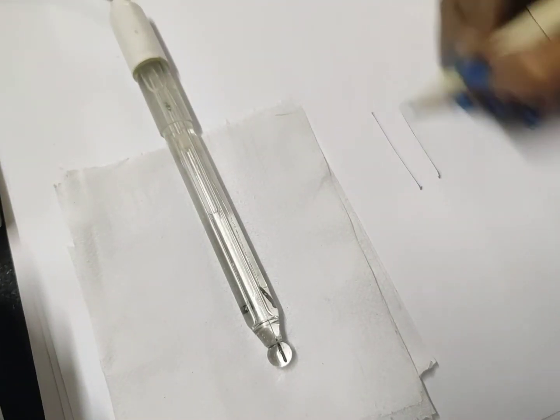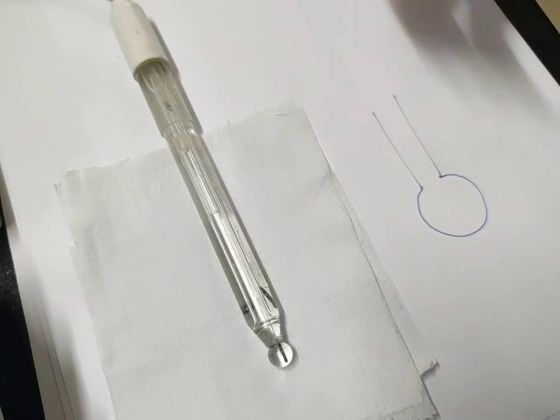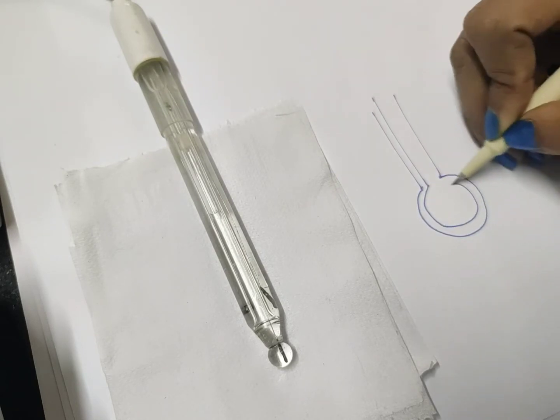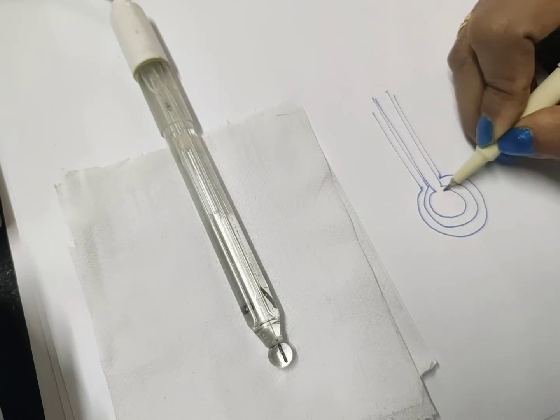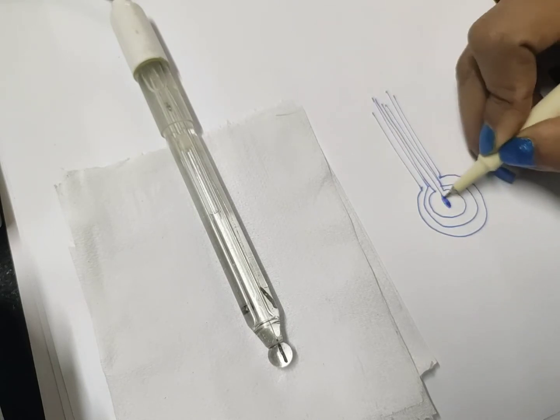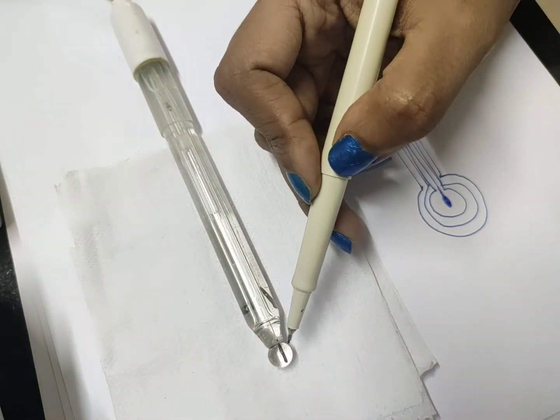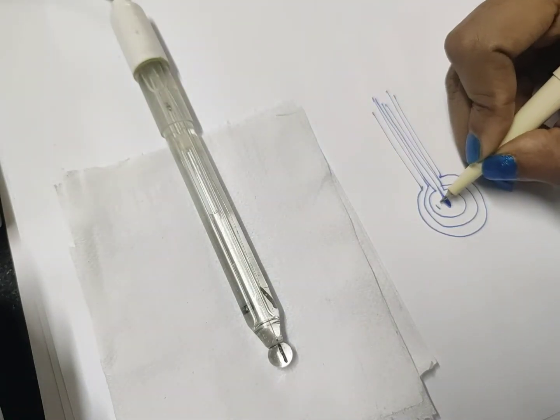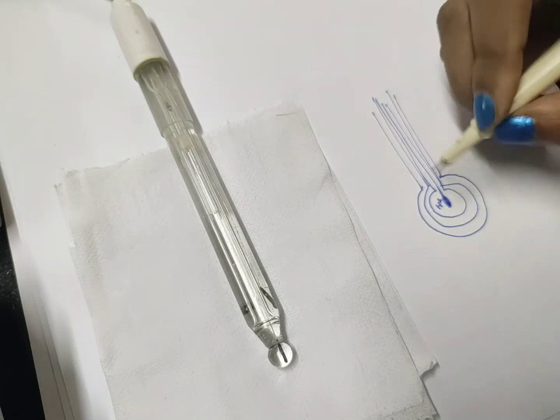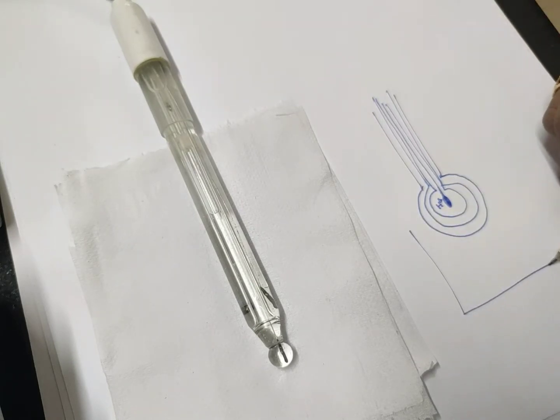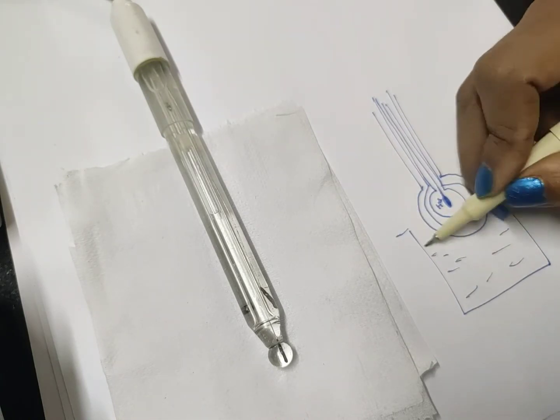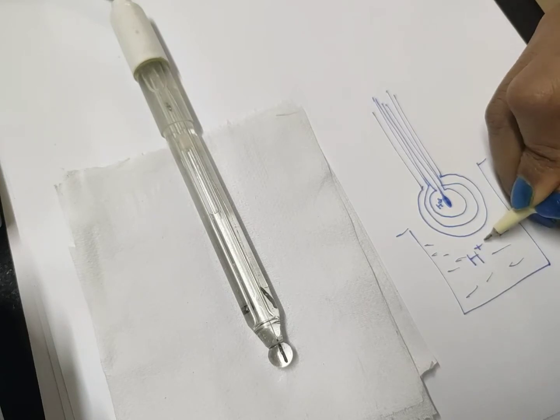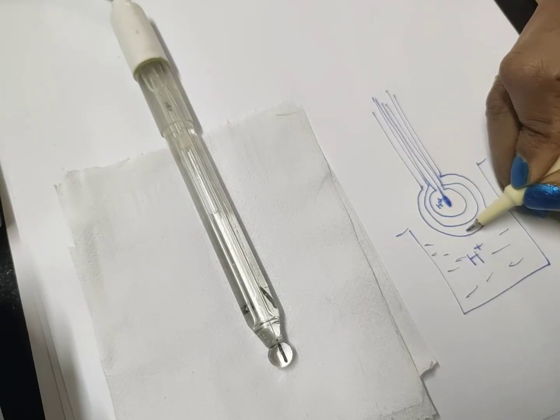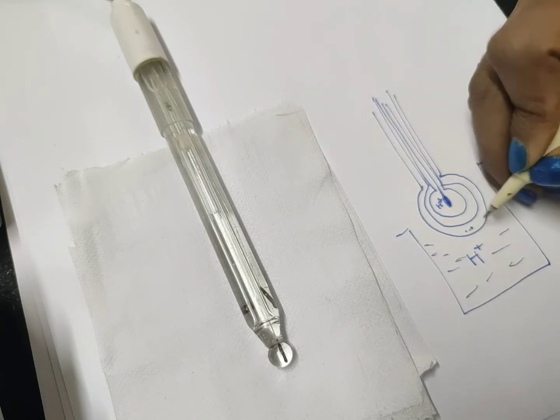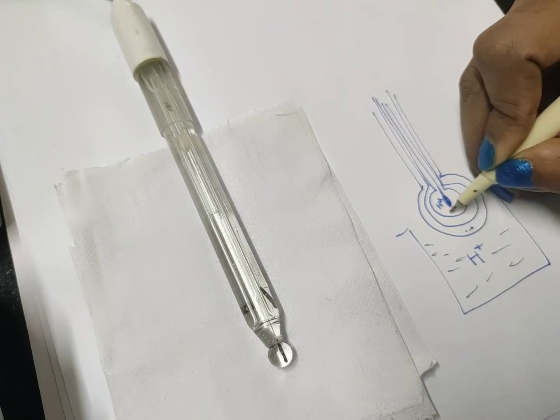So it looks kind of like this. Obviously we cannot see it with our eyes, but inside it is like this, and also one more circle here. This is the electrode that you can see here, the dark one. Inside it is filled with 0.1 normal HCl solution. Now suppose you are dipping this electrode in a glass beaker where your sample has been kept. If the hydrogen ion concentration in the sample is more, the ions will migrate till this layer, and now it will sense how much hydrogen ion is here.